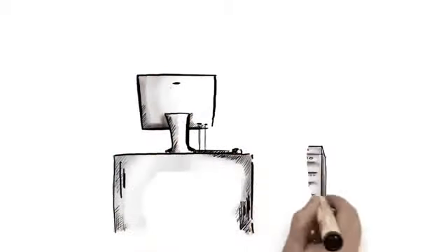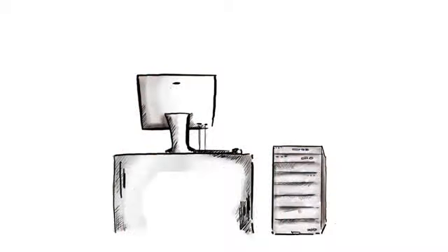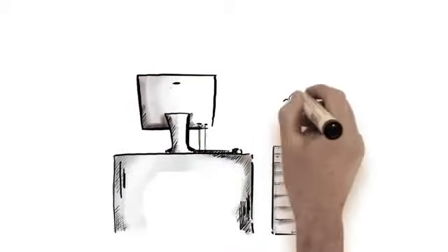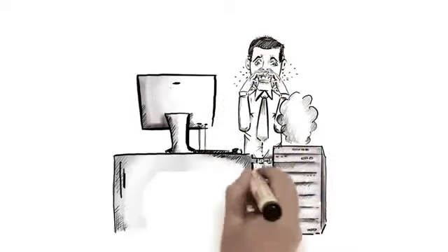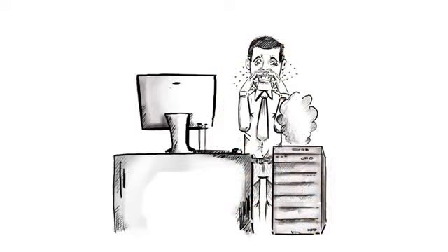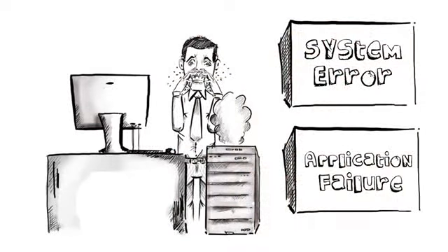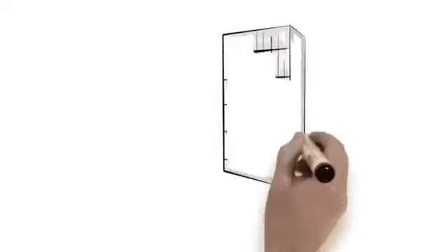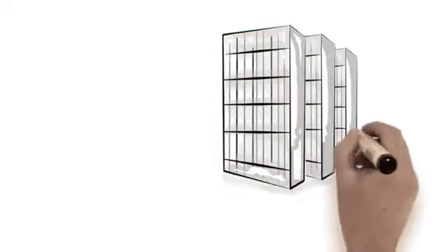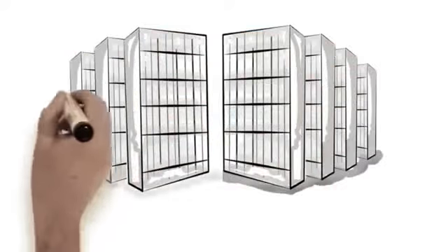A server running a few degrees too high will suffer from CPU calculation errors. Those result in application failures. When a server runs too hot, the fans will be stressed. This may result in a failure of the server. A server failing means that your business operations continuity is affected. Therefore, temperature monitoring at a rack level is a must and not an option.